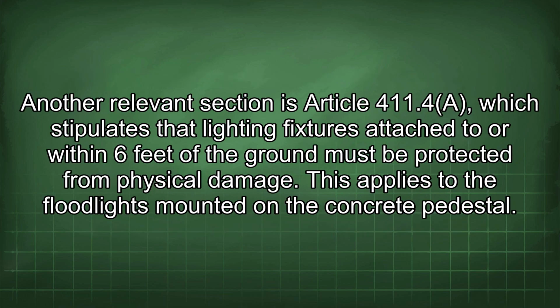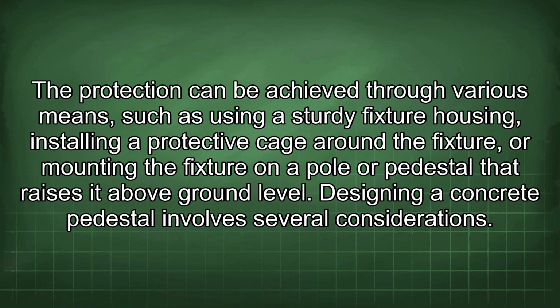Another relevant section is Article 411.4a, which stipulates that lighting fixtures attached to or within 6 feet of the ground must be protected from physical damage. This applies to the floodlights mounted on the concrete pedestal. The protection can be achieved through various means, such as using a sturdy fixture housing, installing a protective cage around the fixture, or mounting the fixture on a pole or pedestal that raises it above ground level.